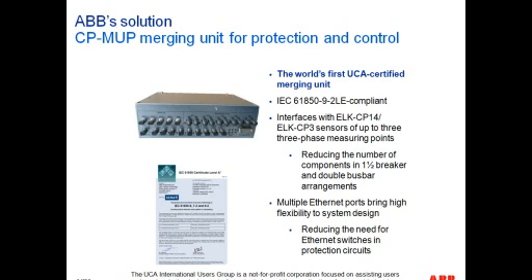And this particular merging unit has multiple Ethernet ports, so that there's a reduction in the need of Ethernet switches in protection circuits. So you could essentially utilize the different ports in your merging unit to create your process bus network without the need of additional switches.